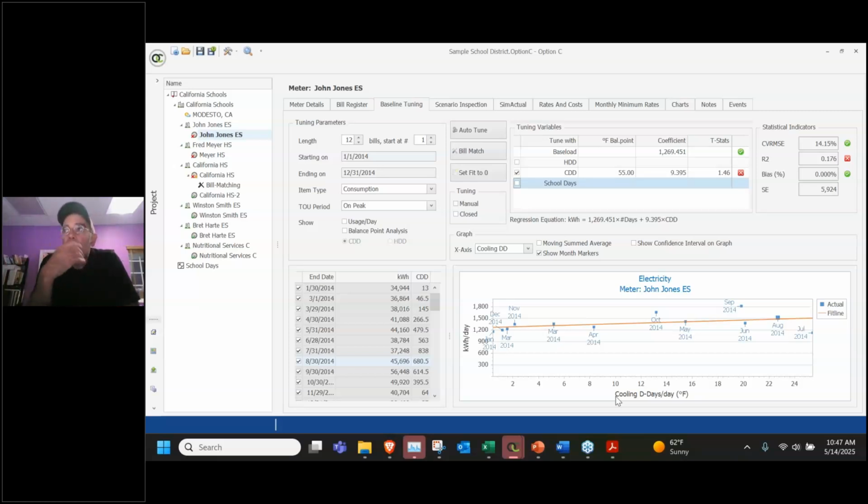And that's why the R squared really isn't a great indicator, because if you're in San Francisco or Hawaii where the weather doesn't really change much, you're always going to have a bad R squared value. It's dumb. And so you try to use R squared, you're never going to say you have a good fit. And so, yeah, I'll leave it at that.